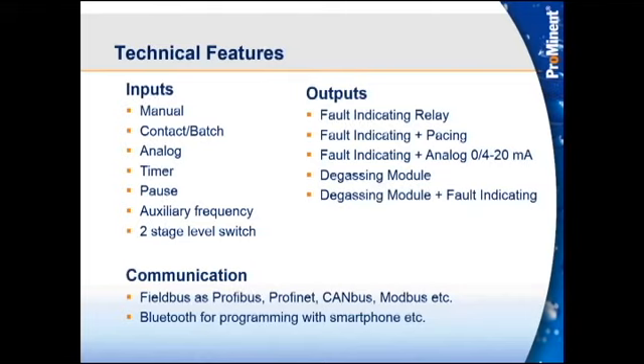And once you're in there, you can change a lot of different modes in the pump. In that simulation mode, it's going to ask for a password. In simulation mode, you can put in any password to get into the next menu. If you have an actual pump in front of you, you would go into the programming, turn on the Bluetooth mode, sync it with your phone. When it asks for a password, the default password on our pumps when they leave the factory is going to be the last four numbers of the serial number. Okay. Once you're in there, you can pretty much change a lot of the settings in the pump.